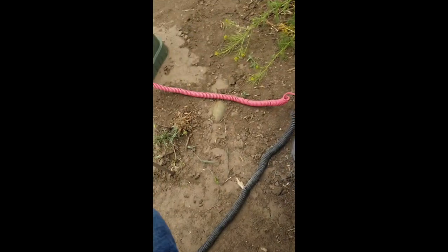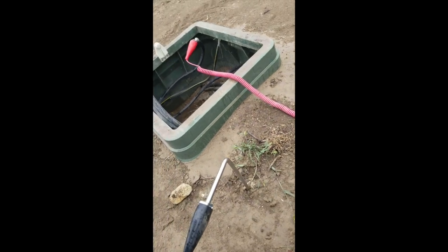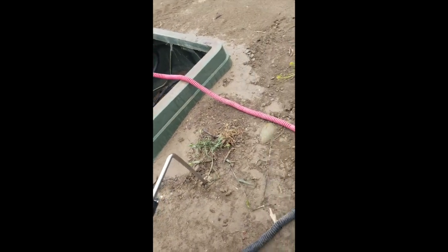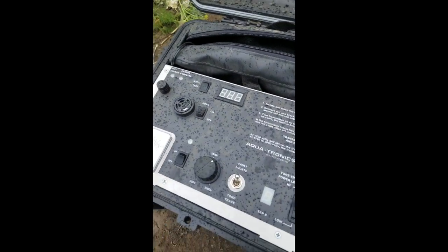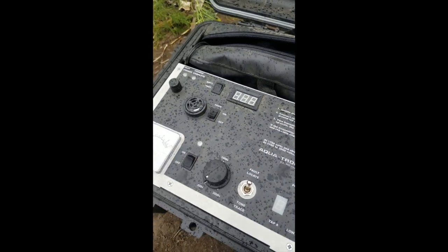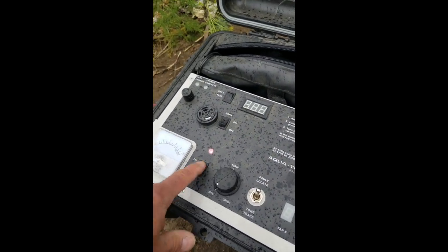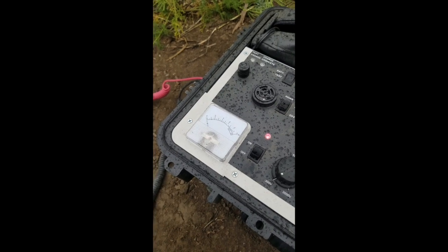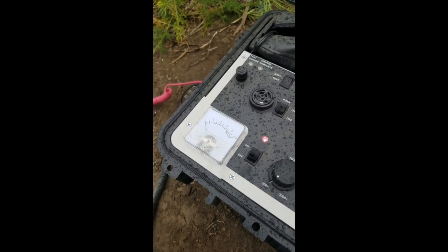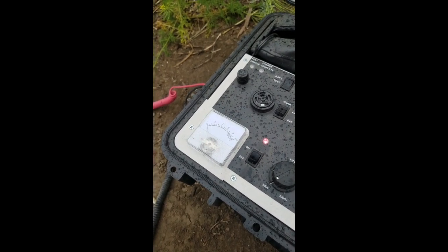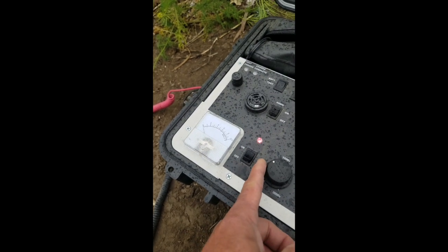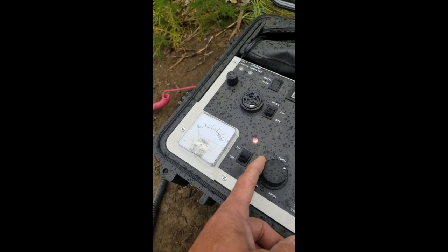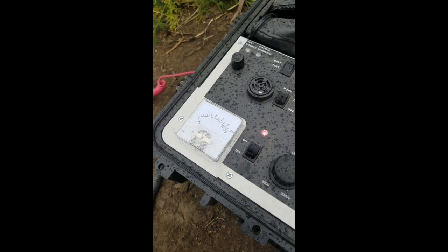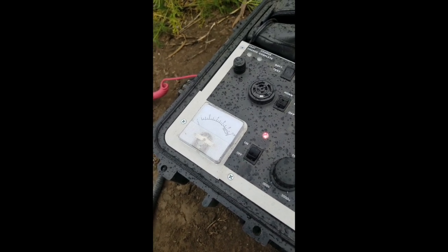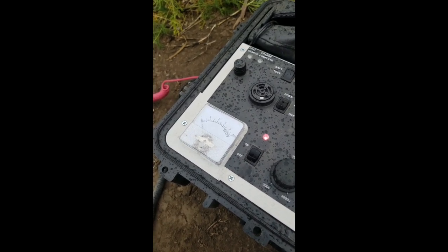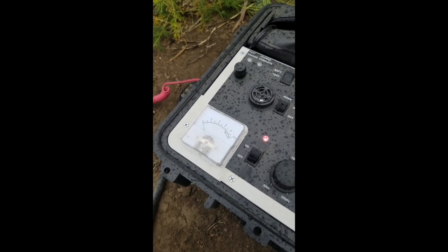What I've done here is I've connected to a simple little secondary run in a test yard, just to show you kind of what would happen on a good cable. I turn the device on, you see the meter really isn't doing anything. We're not showing that there's a fault, so I'm going to just start throwing some voltage to it. When we get up above 1500 volts, you can see that there's a negative deflection on that meter. That shows me there is no fault. This is a good cable.